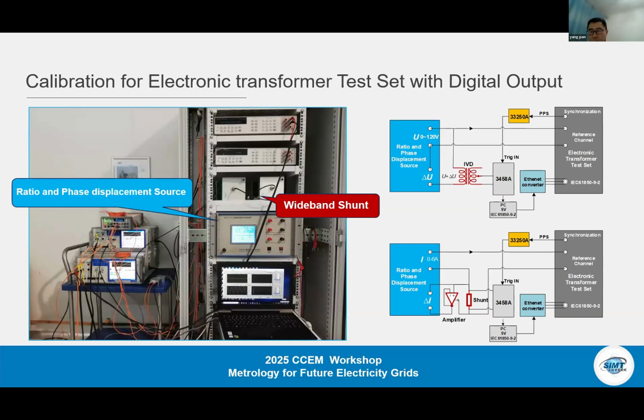So commercial electronic transformer test sets may incorporate functionality for testing both ECT and EVT. A ratio and phase displacement source, typically used for calibrating conventional transformer test sets, was employed to generate the reference current or voltage and differential current or voltage. The reference current or voltage is applied to the analog input of the electronic transformer test set. This reference signal with a superimposed differential current or voltage is digitized using the DMM. All sample data are then packetized according to the protocol and transmitted through the Ethernet interface of the computer, via Ethernet to fiber conversion, to the digital input of the electronic transformer test set.